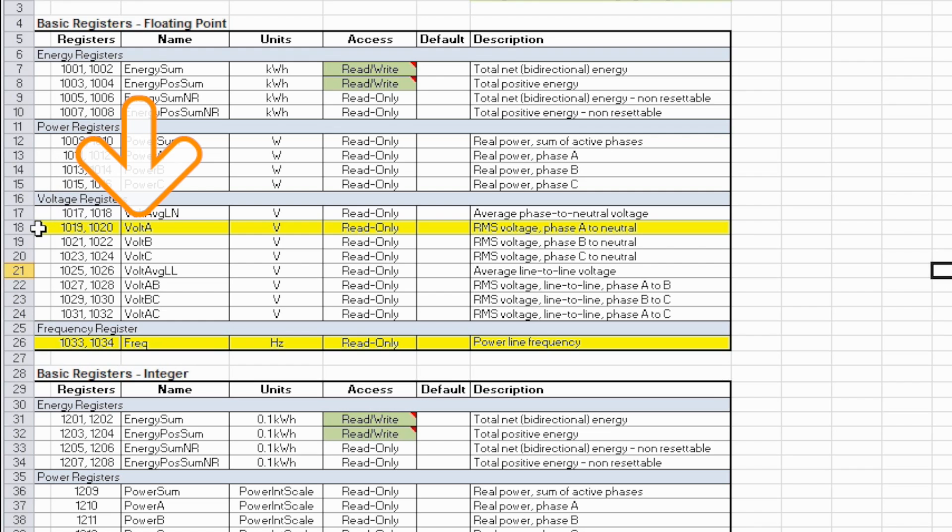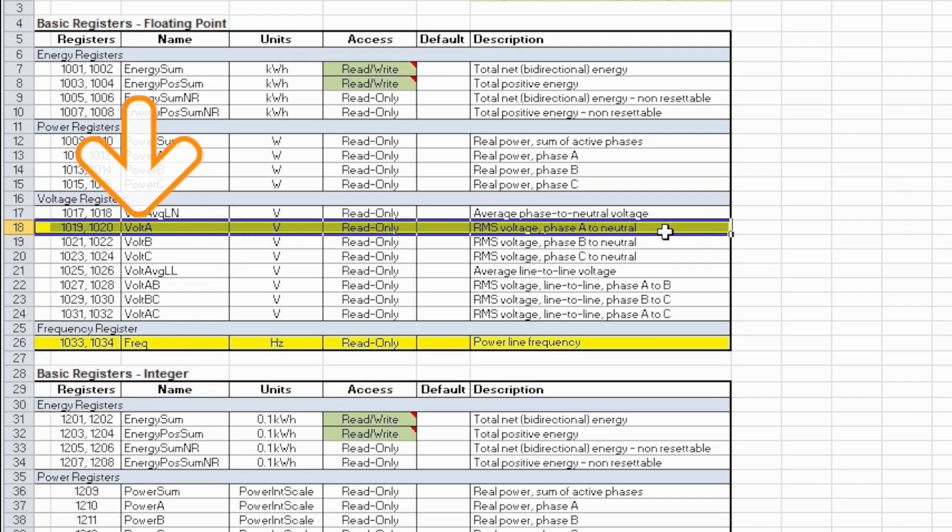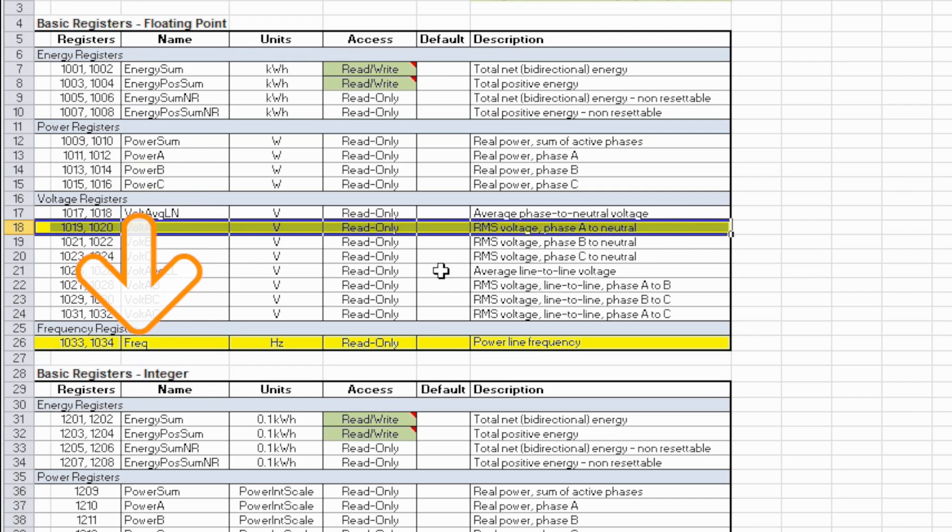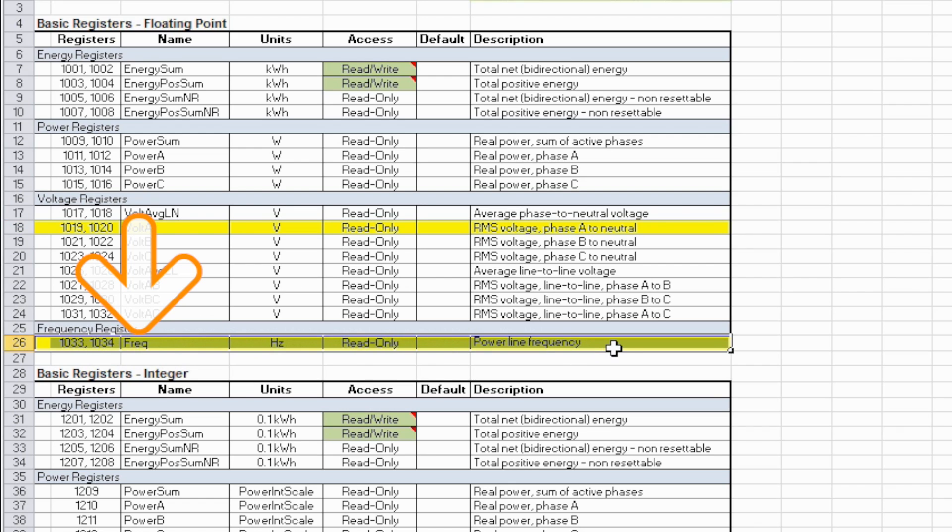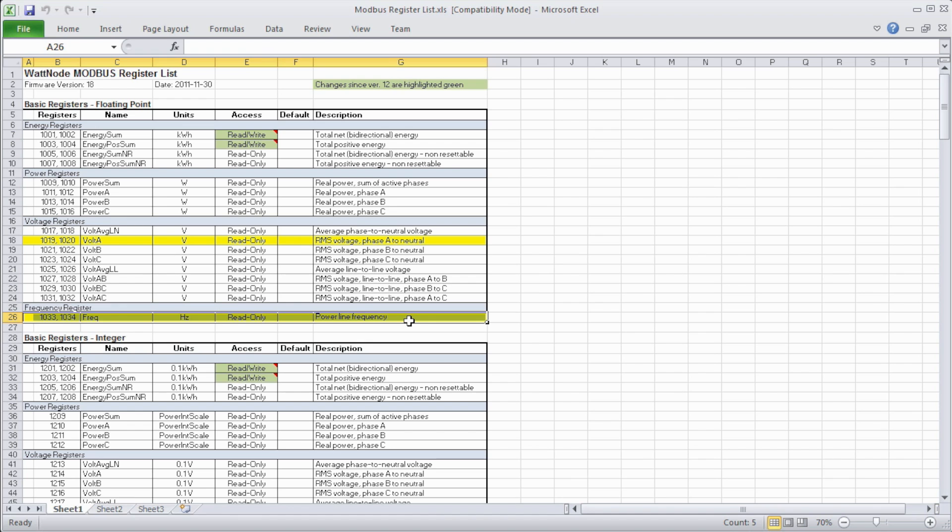I'll be using voltage, which is a float value that starts at register 1019, and frequency, which is also a float value, which starts at register 1033. These numbers are critical and I'll show you why in a minute.